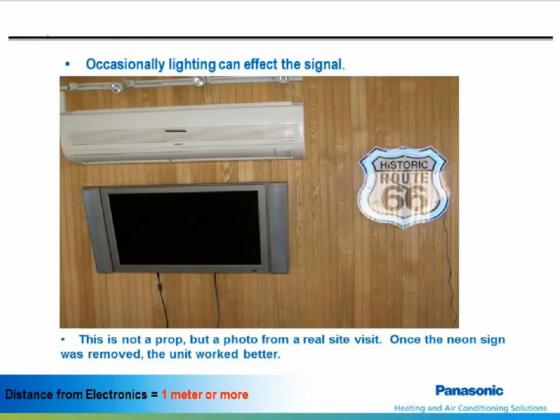The wireless remotes use an infrared communication signal, and bright lights can weaken or interfere with the signal. In this example, removing the neon sign allowed the remote to control the unit properly. Two other potential problems with this example are a clogged condensate line could damage an expensive TV, or the heat rising from the TV could cause a continuous call for cooling. If it were in the heat mode, it might prematurely satisfy before the room has reached set point.